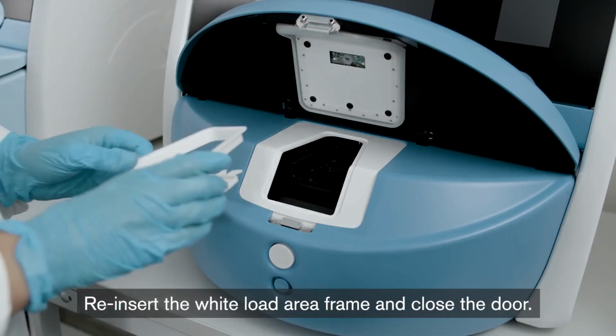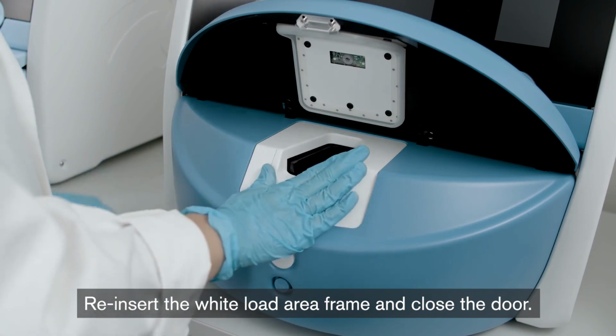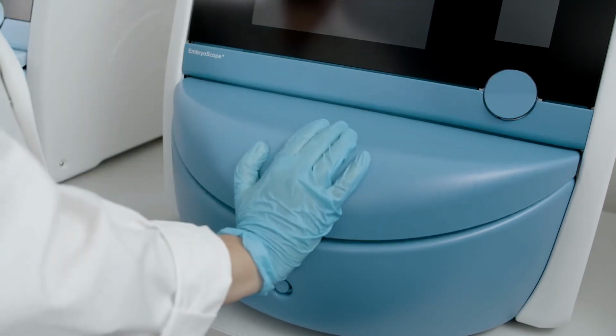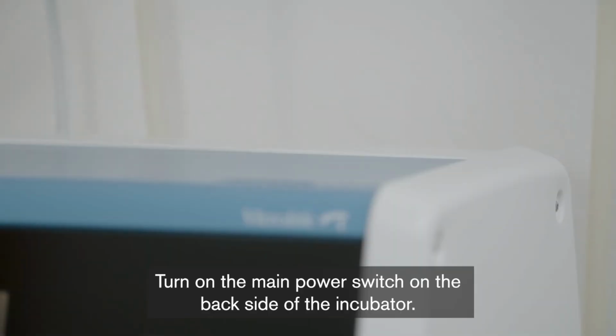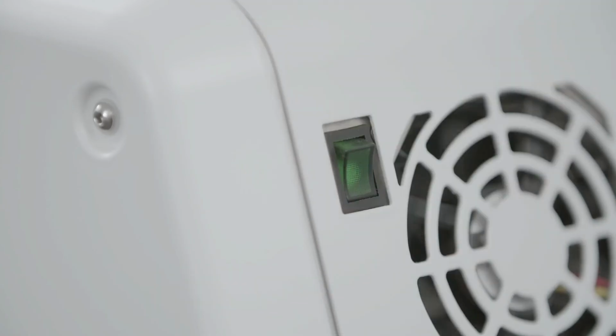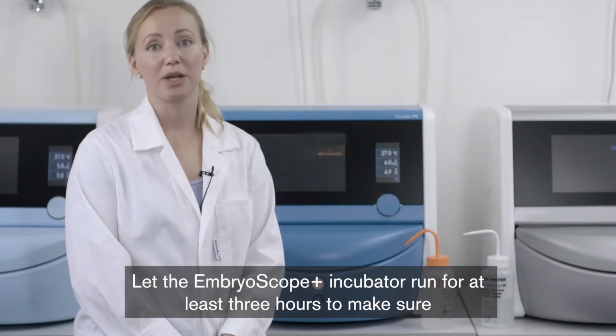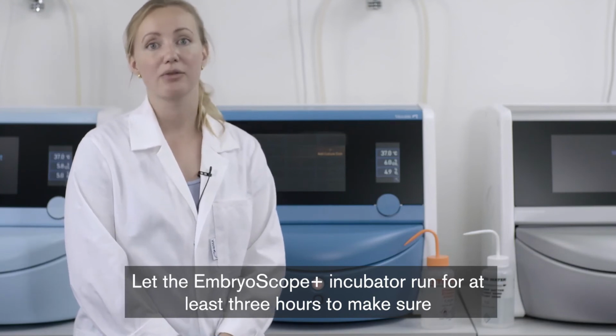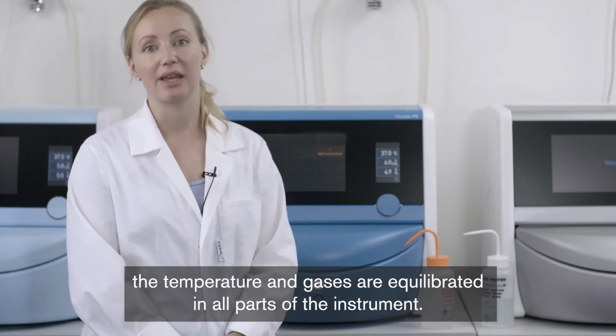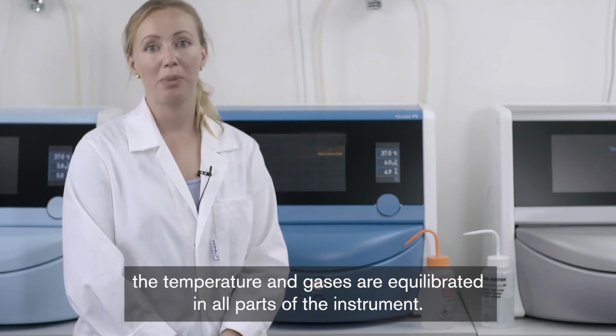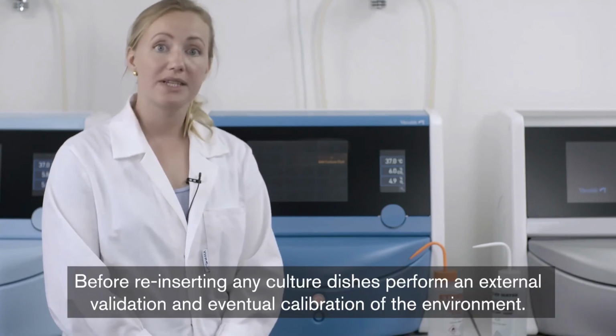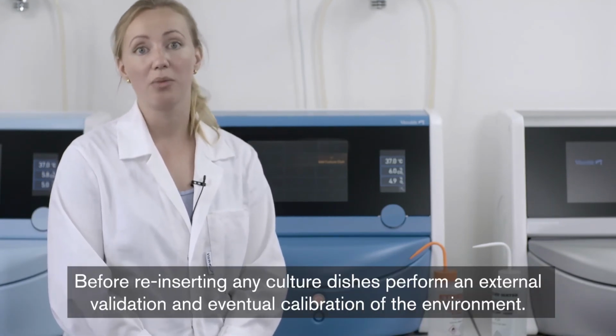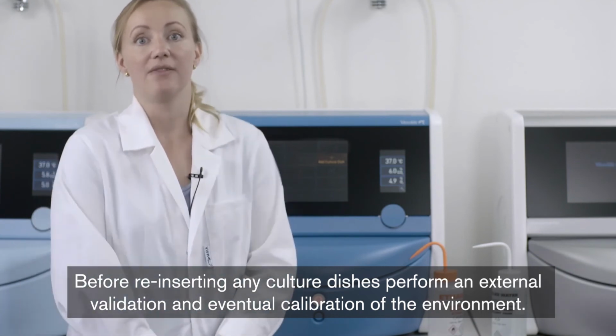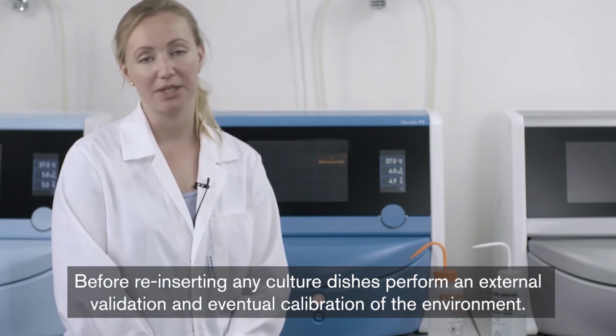Reinsert the white load area frame and close the door. Turn on the main power switch on the backside of the incubator. Let the EmbryoScope Plus incubator run for at least 3 hours to make sure the temperature and gases are equilibrated in all parts of the instrument. Before reinserting any culture dishes, perform an external validation and eventually calibration of the environment.